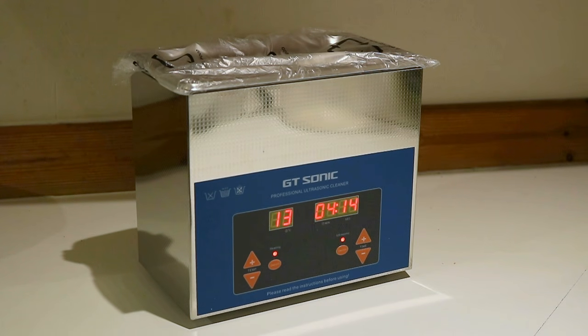As I was saying, you can put warm water in there, but it must be warm. Never ever put boiling water in there, because the transducers, which are attached to the underside of the tank, will have the adhesive bonding them melted by boiling heat, and they'll fall off, and the machine won't work. So warm water, anything up to 50-60 degrees, but never boiling.